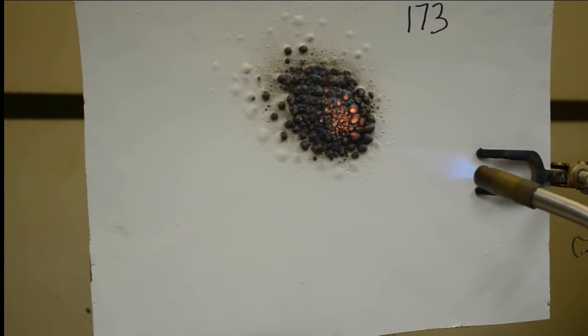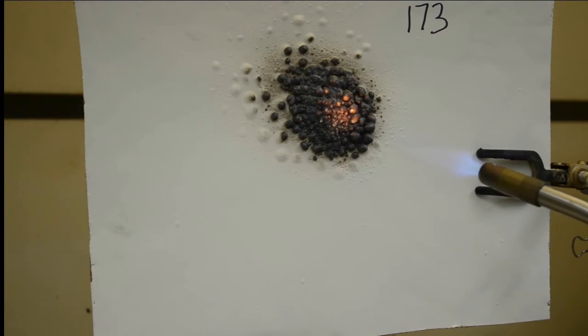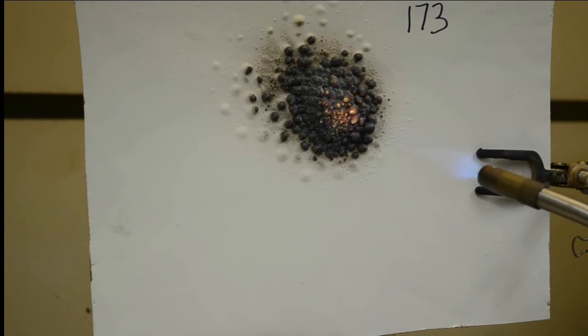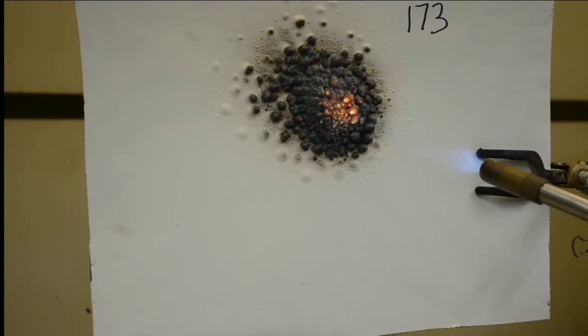Flame Control 173 has been subjected to rapid rise fire conditions and maintained the permissible temperature performance criteria as specified in the UL1709 and ASTM E119 tests for a period up to two hours.